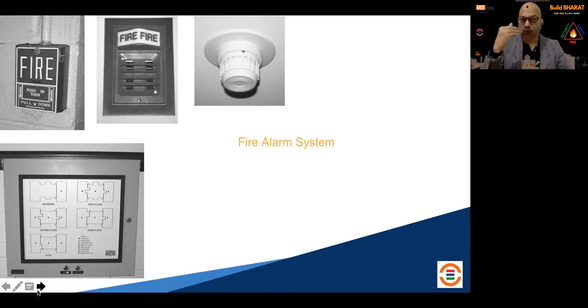Manual call point is supposed to be visible and accessible at a height not more than 1.2 meter, because somebody can press it just like that. But if it's kept in an area which is not accessible, not visible, or not operable, your purpose is entirely gone - because it's not being inspected during construction, not shown correctly in the drawing, or not interpreted rightly by the construction guys.